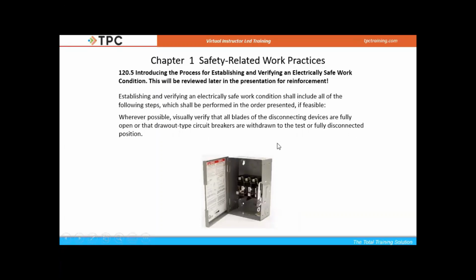With a disconnect about the size of this one, it's important, but when we get into very large disconnects at higher voltages it becomes extremely important. I had a friend doing a job one time at 4160 volts. He pulled the disconnect down, no problem, but he never looked in to see if all those blades had actually opened up. When he stepped into that, the electricity arced over, caught his clothes on fire, third-degree burns over 40% of his body.